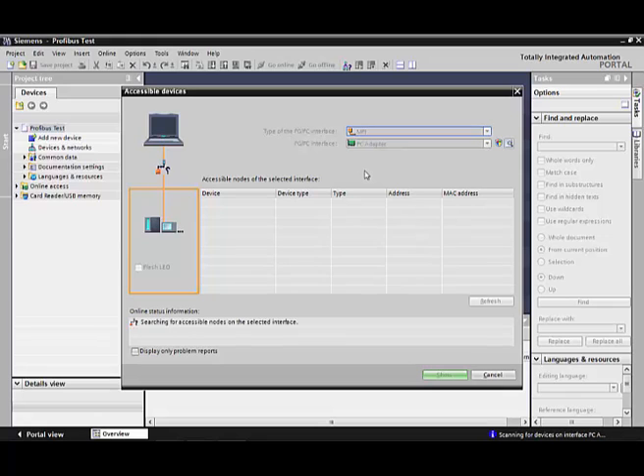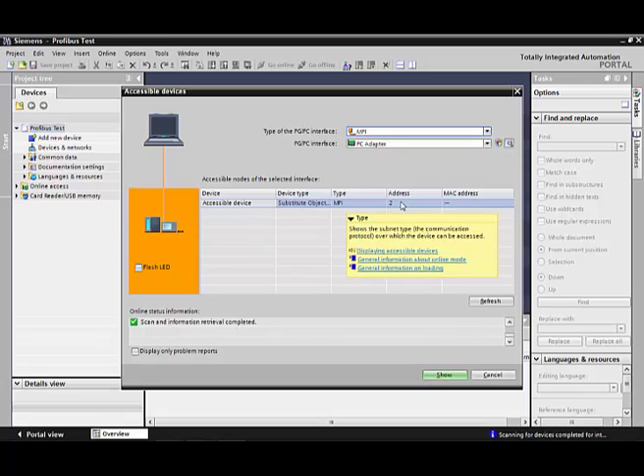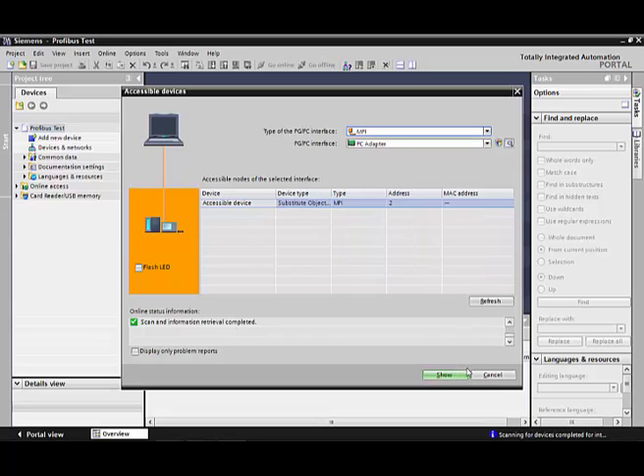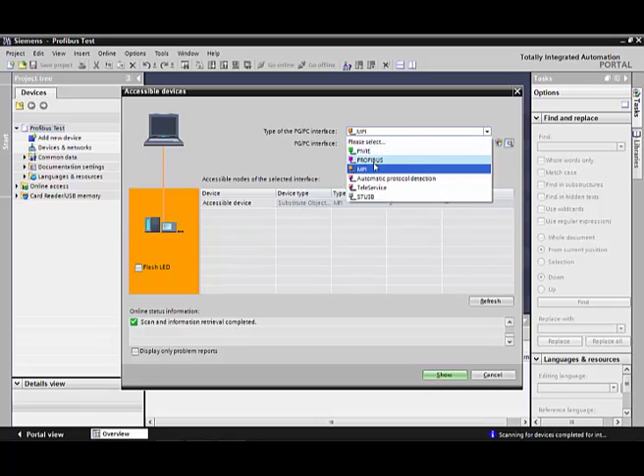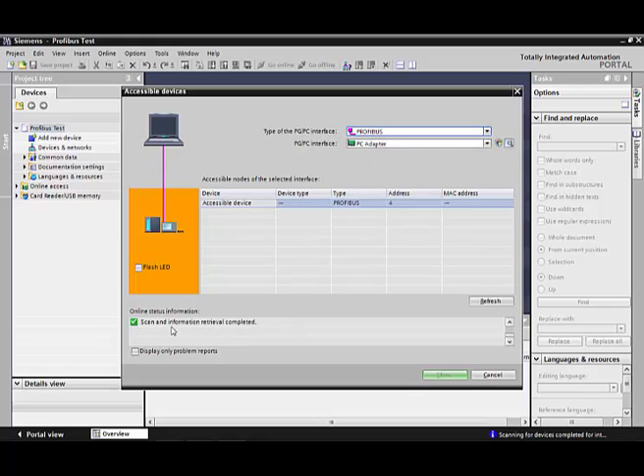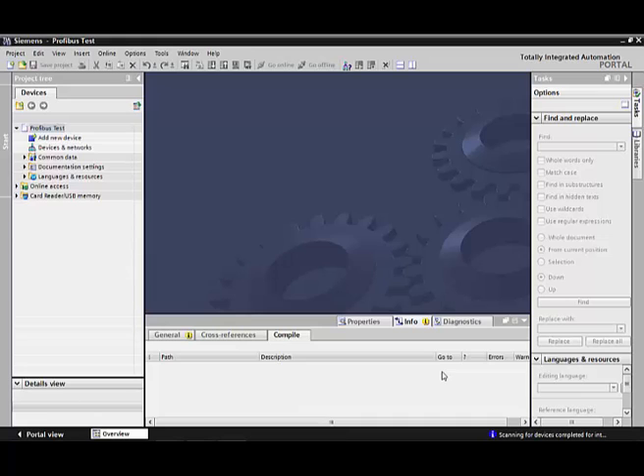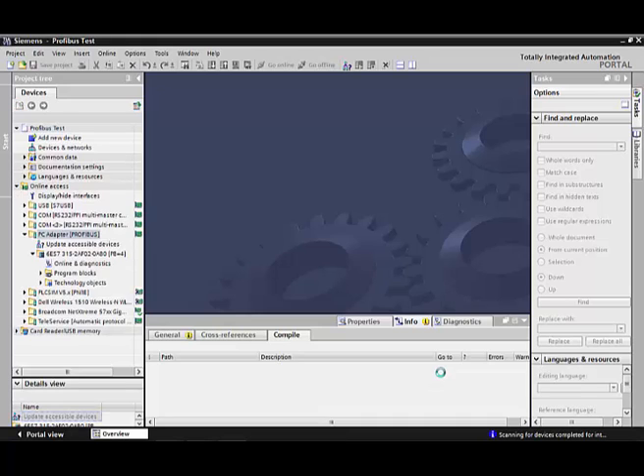So now, you change that to MPI. We'll change the same DB9, and we'll plug it into the next port over because we're on a 315-2DP processor. So it has MPI and Profibus on the same processor. And all you have to do is pull out the DB9 end of the cable and plug it into the other port. And then change the PC from going from the Profibus, change it over to the MPI. And then you can access both COM ports on that.